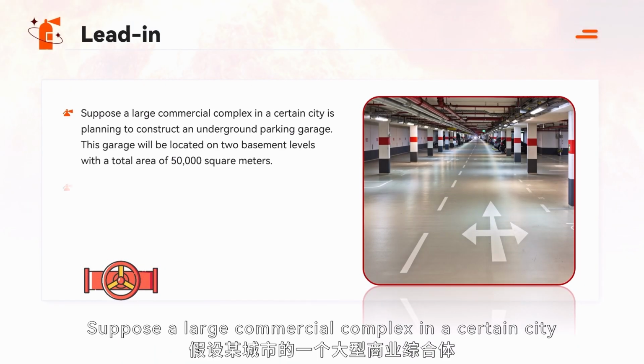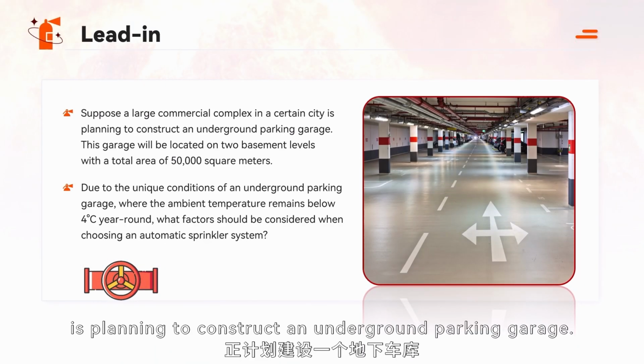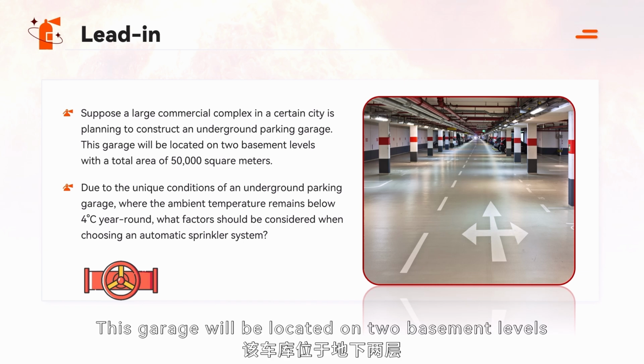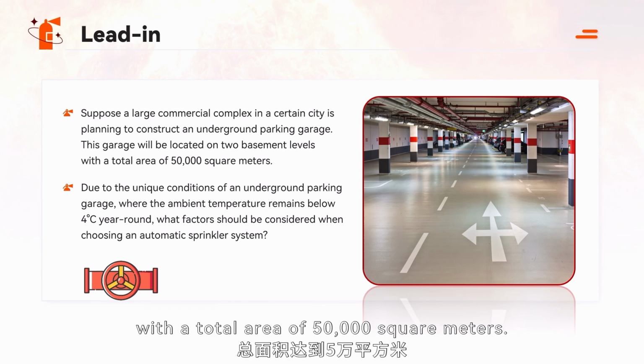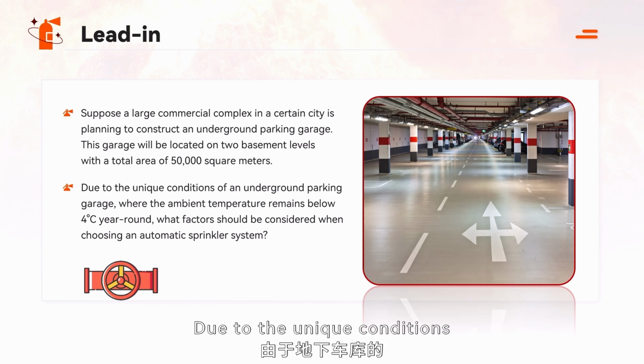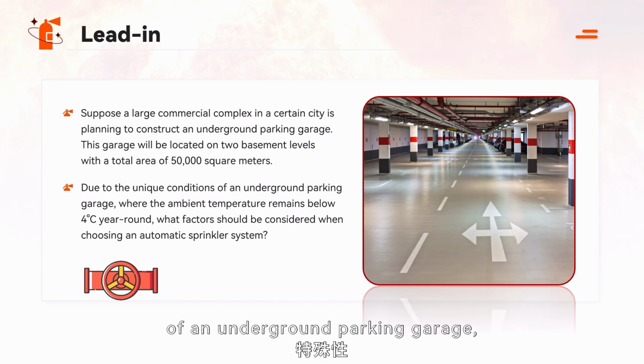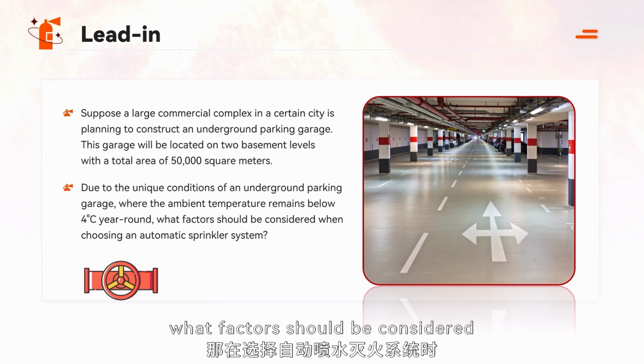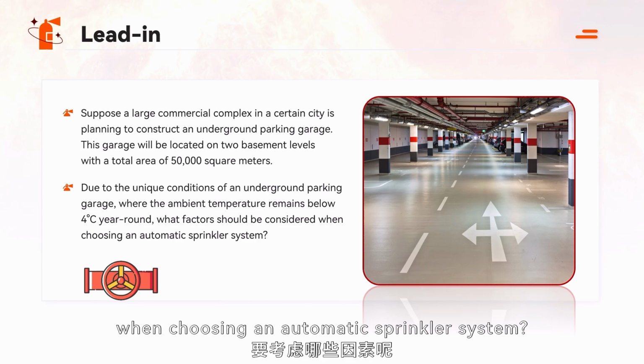Suppose a large commercial complex in a certain city is planning to construct an underground parking garage. This garage will be located on two basement levels with a total area of 50,000 square meters. Due to the unique conditions of an underground parking garage, where the ambient temperature remains below 4 degrees Celsius year-round, what factors should be considered when choosing an automatic sprinkler system?